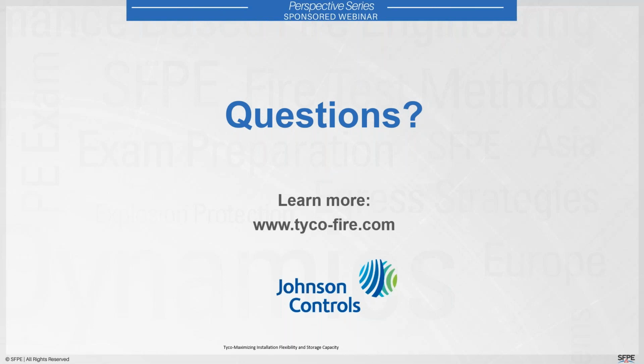Well, thankfully, I'll try to answer this one quickly. Essentially, the feedback that the NFPA committee got from people using the book was that the book was becoming very challenging, and that designing sprinkler systems using NFPA 13 required readers to bounce back and forth between chapters. What they tried to accomplish was an approach where things would progress from the early chapters to the later chapters based on the occupancy or storage applications. So it tried to minimize the bouncing around that the user of the book would have, and also really wanted to use the book in a manner that paralleled the path of how people design fire sprinkler systems.